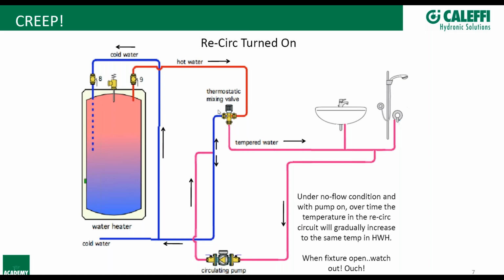And if you don't have the ability to completely close off the hot inlet specifically, you have the ability to add more heat to the loop than what the loop is giving off. Okay, and that's what's referred to as recirc creep, is the idea that temperature is going to creep up. And if you have a long enough time of inactivity, typically overnight, when nobody's washing hands, taking showers, things like that, you have the ability to bring up that entire distribution system and the recirc line all the way up to whatever is being stored in this tank. So the first person that turns on that faucet in the morning has the potential for scalding, and then all of a sudden the mixing valve works great for the entire rest of the day.